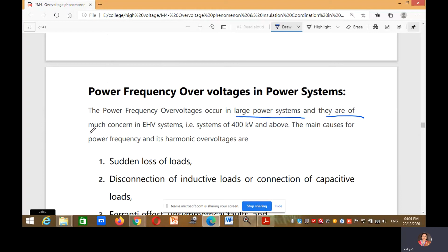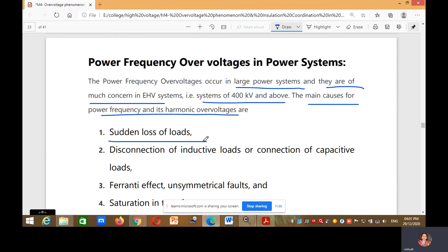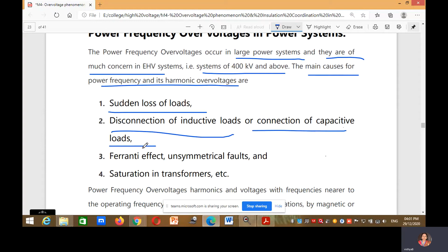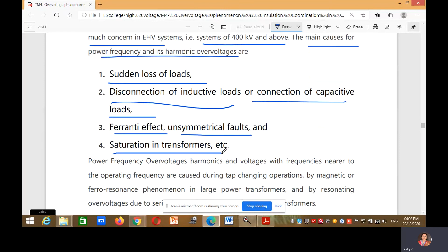The power frequency over voltages occur in large power systems, and they are of much concern in extra high voltage systems, systems of 400 kV and above. The main causes for power frequency and its harmonic over voltages are: sudden loss of loads, disconnection of inductive loads or connection of capacitive loads, the Ferranti effect, unsymmetrical faults, and the saturation in transformer.